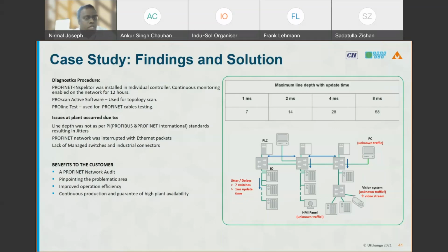The issues we identified were primarily jitter issues, and a lot of Ethernet packets moving around in the PROFINET network, which pushed the net load above the recommended standards. Also, the switches used were not managed switches. All three of these things need to be noted during any commissioning of the plant, to ensure a better and more stable network - this is a very important step to consider.